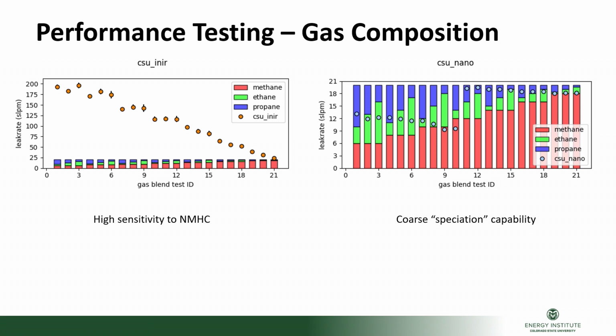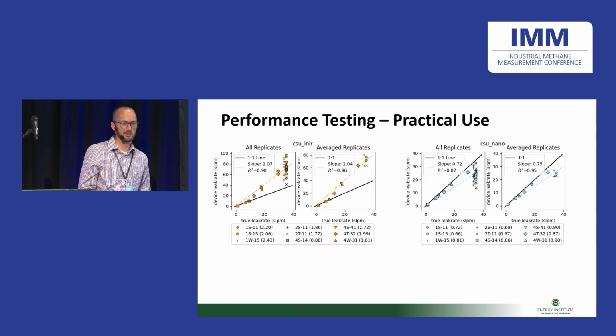So here's the interesting thing with the gas composition response. On the left, you can see the CSU INIR sensor is very sensitive to higher hydrocarbons. We've got basically 100% methane on that end and moving down to about 30% on this end, and our response swings by like a factor of 10. And the idea was to run the nano with the same blends and see how granular we could get. It turns out that we only got 2 different steps in the differentiation. We swung from 90% to 30% methane, and it only gave us 2 steps, so it said this is a methane blend and this is a light gas blend. So that was probably not going to be useful to do our total calibration curve correction and manipulation.